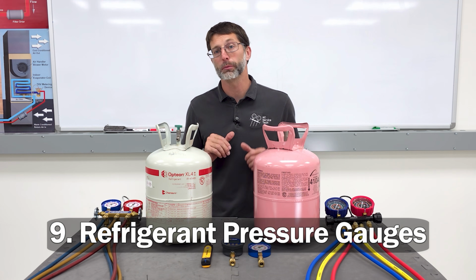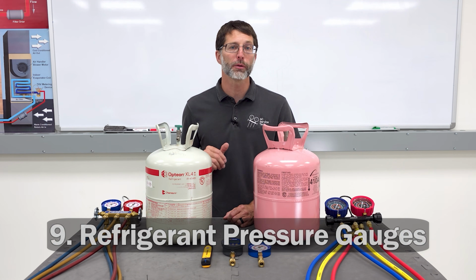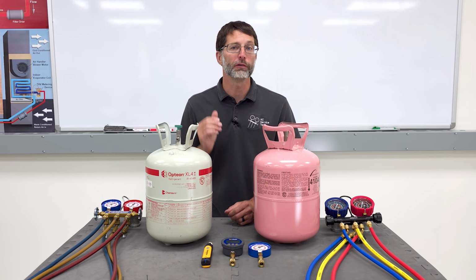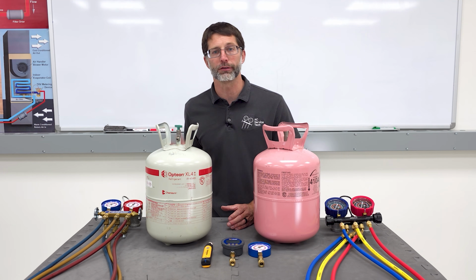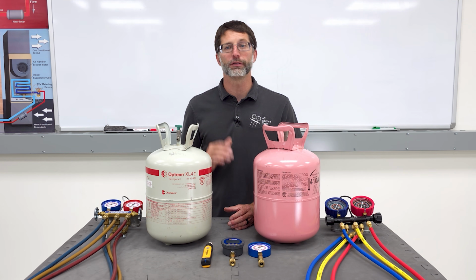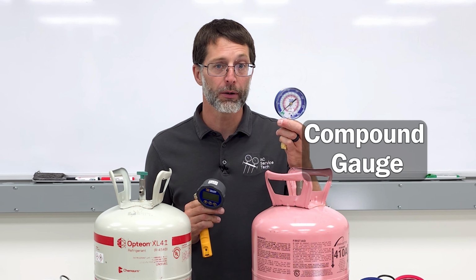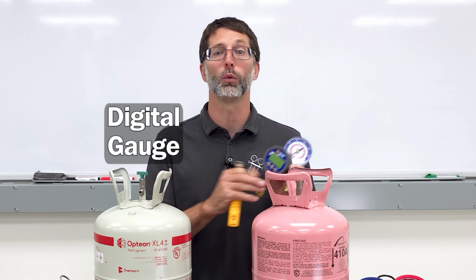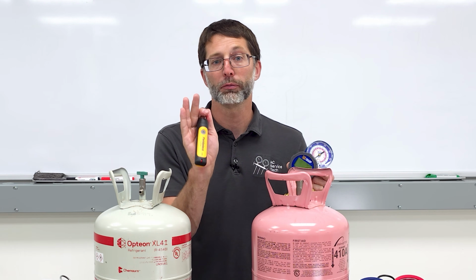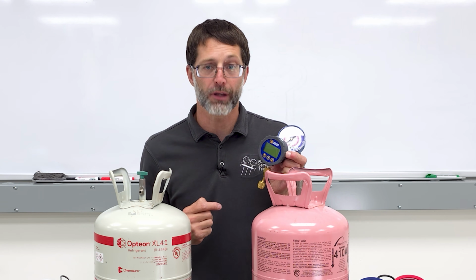Section 9, Refrigerant Pressure Gauges. In order to measure the pressure of a bottle, an off and equalized system, or a running system, a pressure measuring device is needed. This device may be a compound gauge, a digital gauge, or a wireless pressure probe. Wireless probes are discussed in Section 12. The main purpose for measuring pressure is to convert the pressure to saturated temperature.